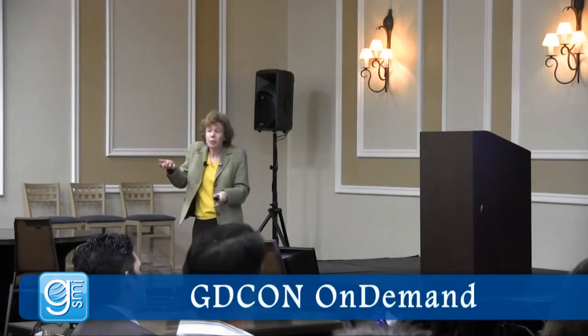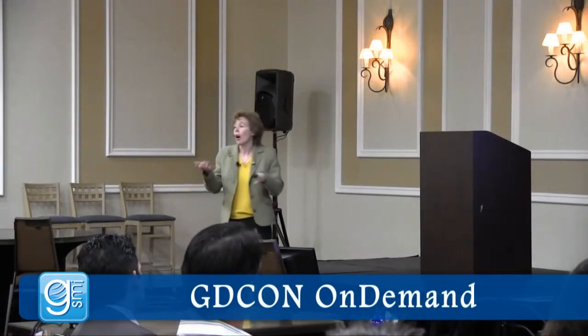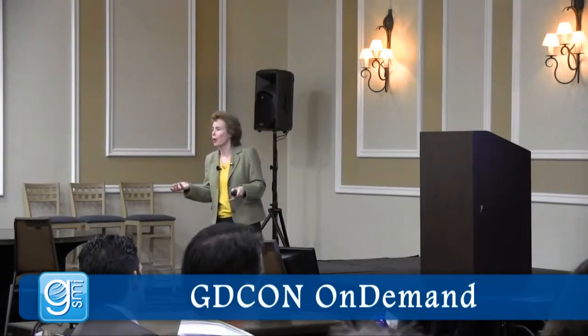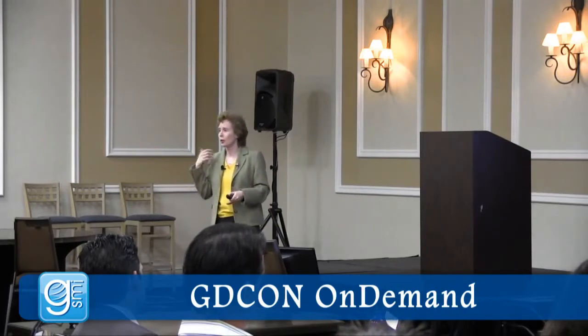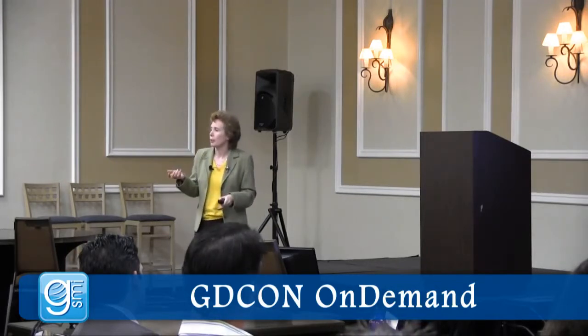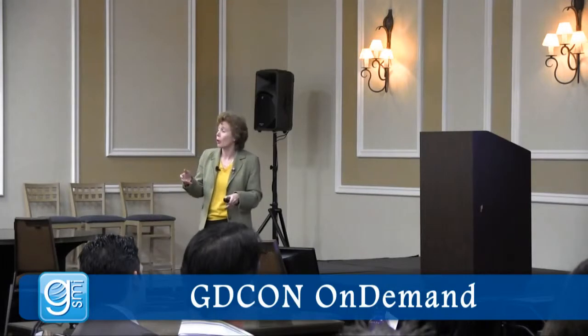One thing you need to pay very close attention to is things like relative humidity. You watch what's happening in the weather coming down the pike and get ready to adjust the data center accordingly. If you're going to have a dew point of 80 degrees, you need to let the data center go up to about 86 degrees so you don't get condensation on the servers. This is something that if you just brute force turn on your chillers and ramp them up a bit, you don't necessarily need to accommodate for.